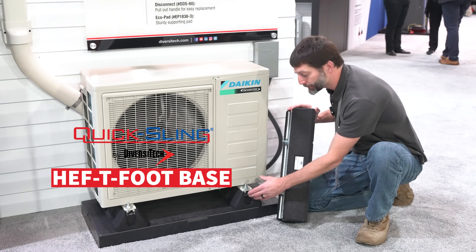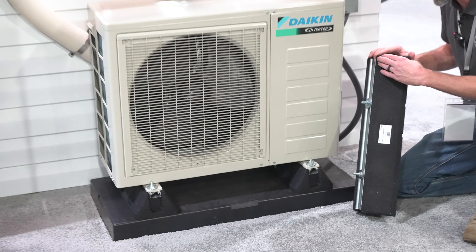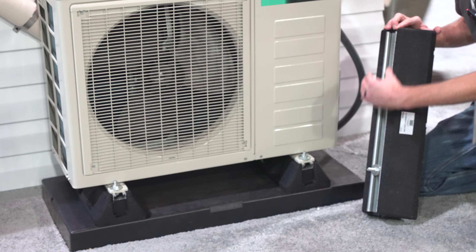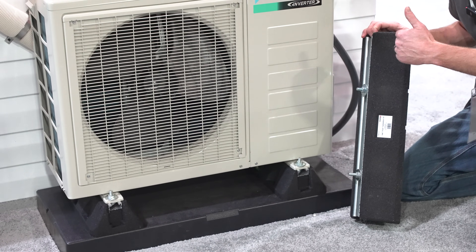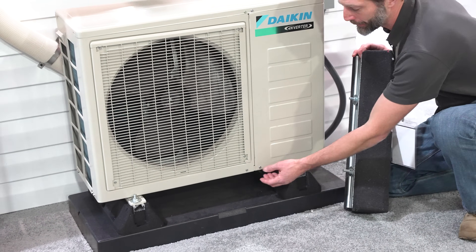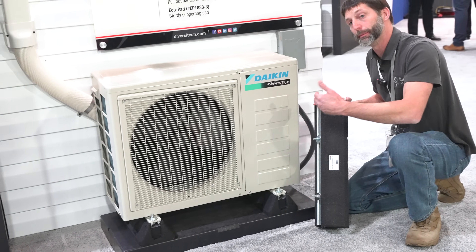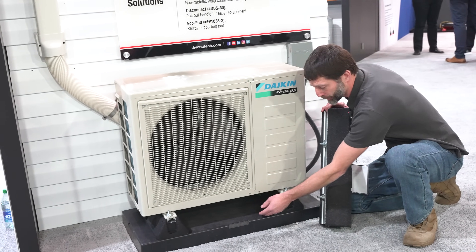Here you have your Hef-T-Foot bases, which come in a two-pack for mounting a mini split. This gets it up off the ground — you have your rubber here and your uni-strut built into it. It's a vibration insulator and also allows any water draining from the system in the middle of winter — since this is a heat pump — to escape, giving it a little space off the ground.